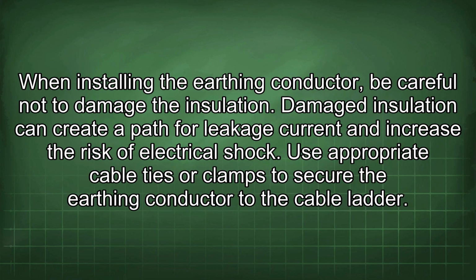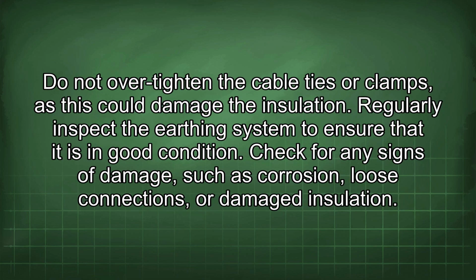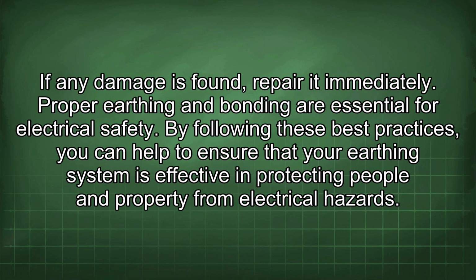When installing the earthing conductor, be careful not to damage the insulation. Damaged insulation can create a path for leakage current and increase the risk of electrical shock. Use appropriate cable ties or clamps to secure the earthing conductor to the cable ladder. Do not over-tighten the cable ties or clamps, as this could damage the insulation. Regularly inspect the earthing system to ensure that it is in good condition. Check for any signs of damage, such as corrosion, loose connections, or damaged insulation. If any damage is found, repair it immediately.